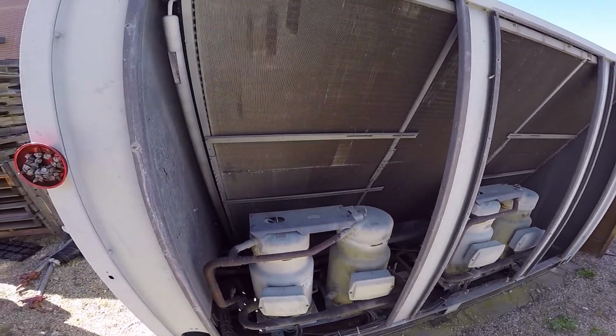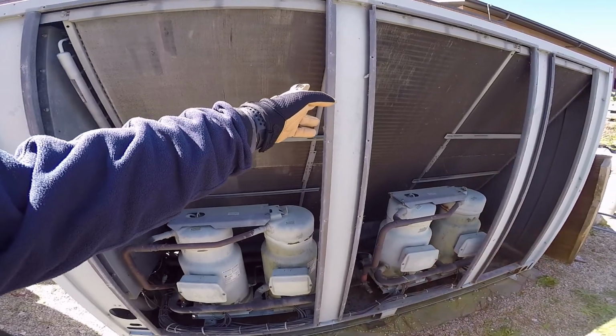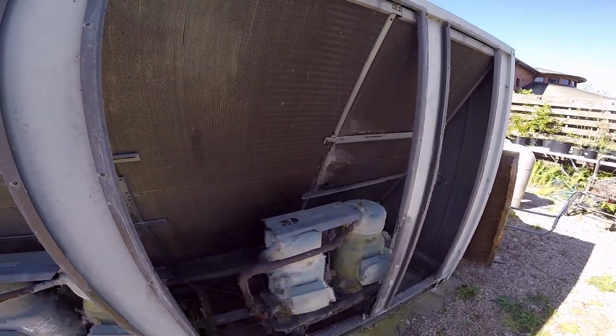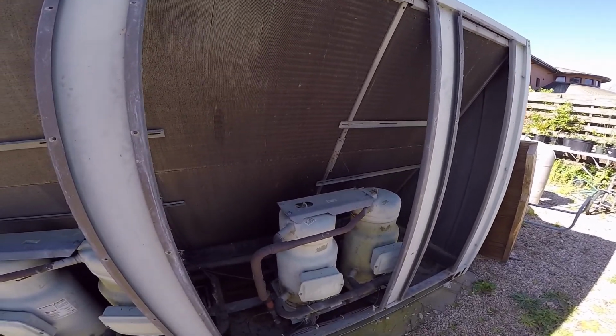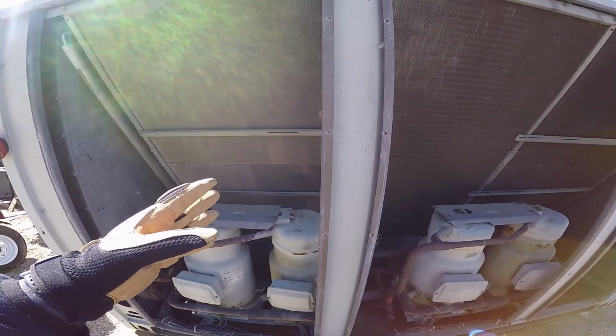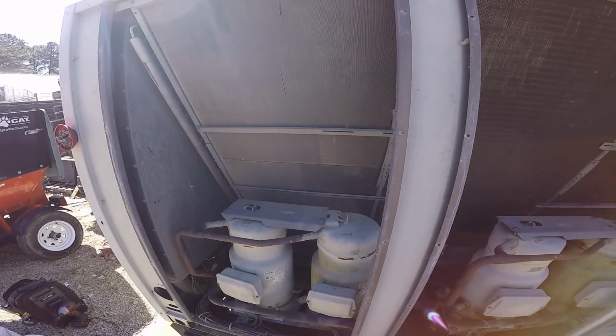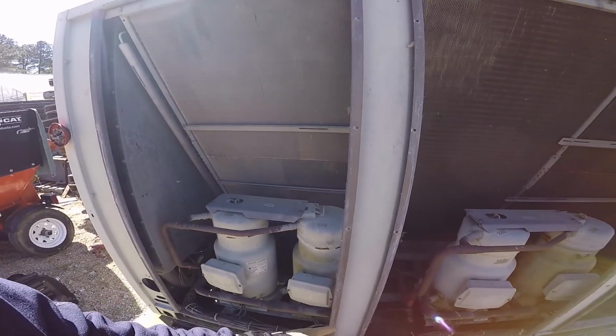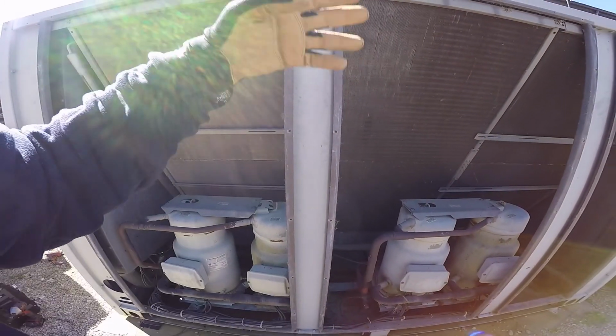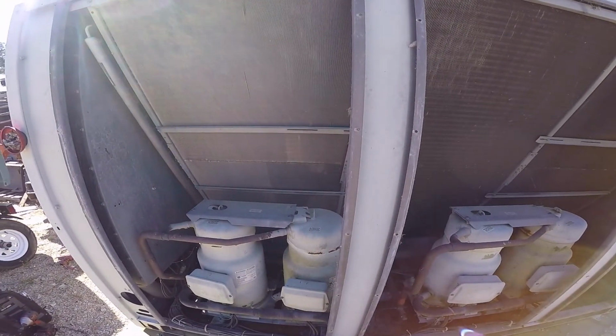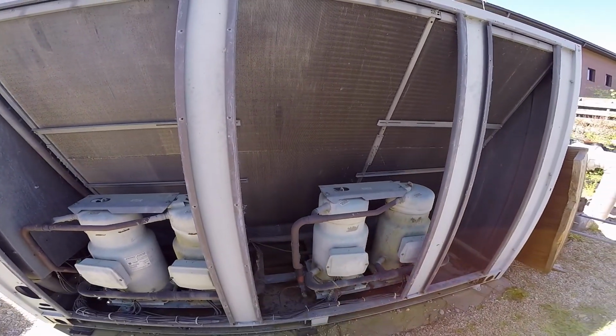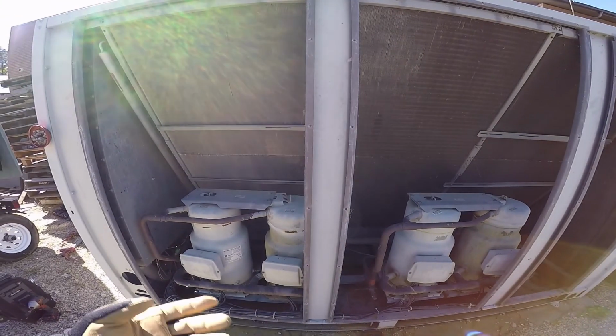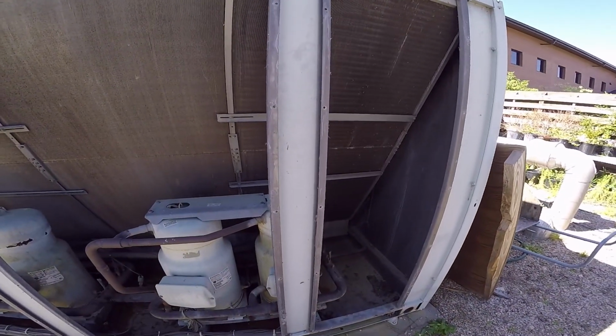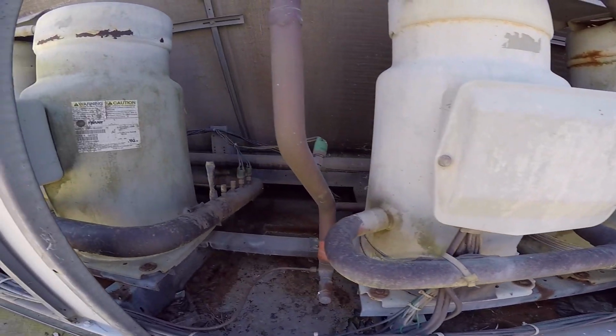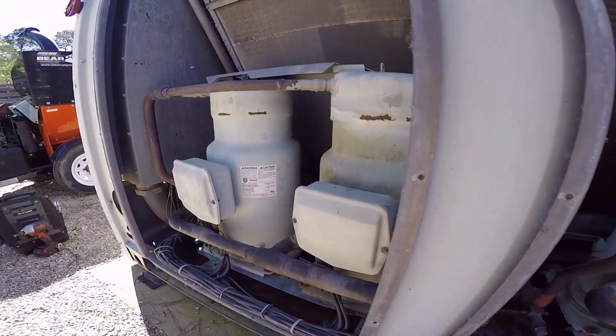All that's really left to do on this chiller, and it'll take some time, is I'll have to wash the coils here with cleaner. One thing I want everybody to keep in mind: before you go up to a chiller and start spraying it with cleaner and corrosives, check your pipes, check around the chiller for oil, because oil is going to indicate a leak. If you wash the coils, the cleaner is going to wash away the oil, and you could be washing away the only evidence that you have a leak. The next time you'll know you had a leak is when the chiller goes out on low pressure or something silly. So before you start cleaning and spraying everything, check all around the chiller, all around the pipes. Put your hands on them, and look for oil.